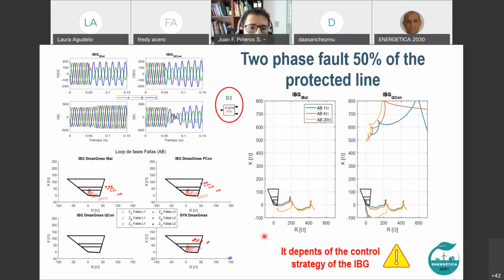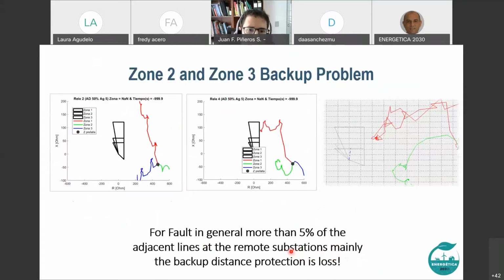An important conclusion about the distance protection performance is that it depends on the control strategy you are using in the inverter-based generation. It is important to say that we really need an accurate model of this kind of generation, because if not, you cannot check or analyze well how the protection will perform. It is very important to have a detailed model of the behavior and the control strategy, because it matters very much.